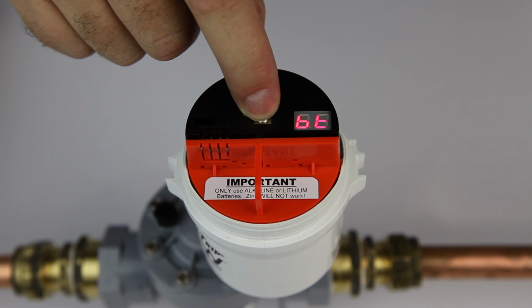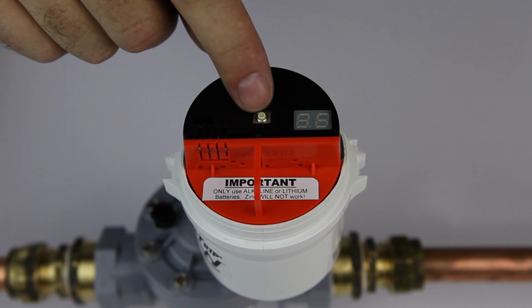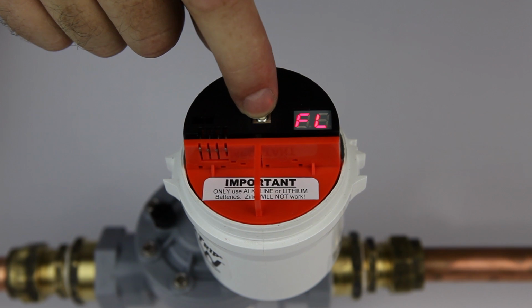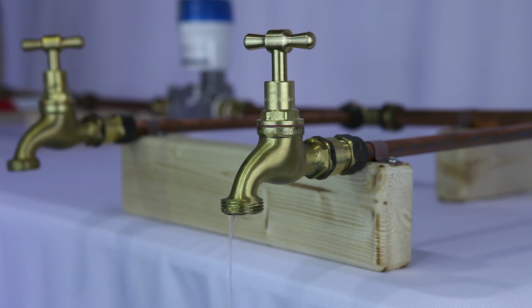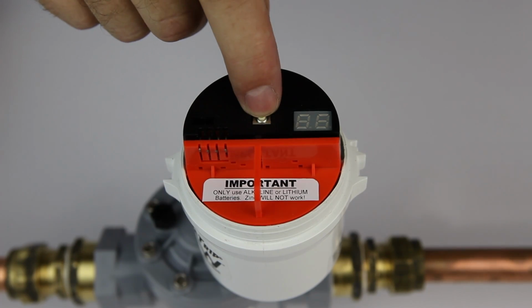If BT battery test appears, it means the flow sensor cannot see the flow. Check the control unit is firmly screwed into the valve and test again. If need be, increase the flow slightly and retest. If flow now registers, then scale the flow back to 40 to 50 mil and check the flow sensor again.